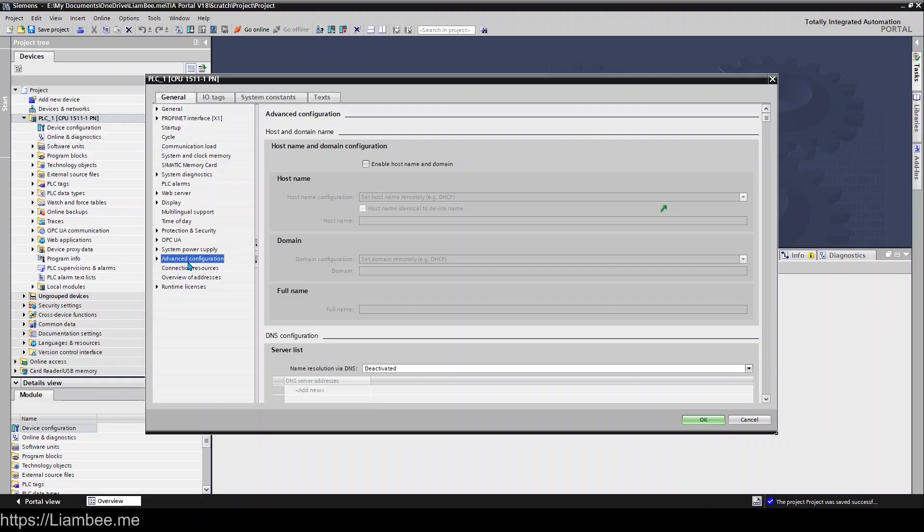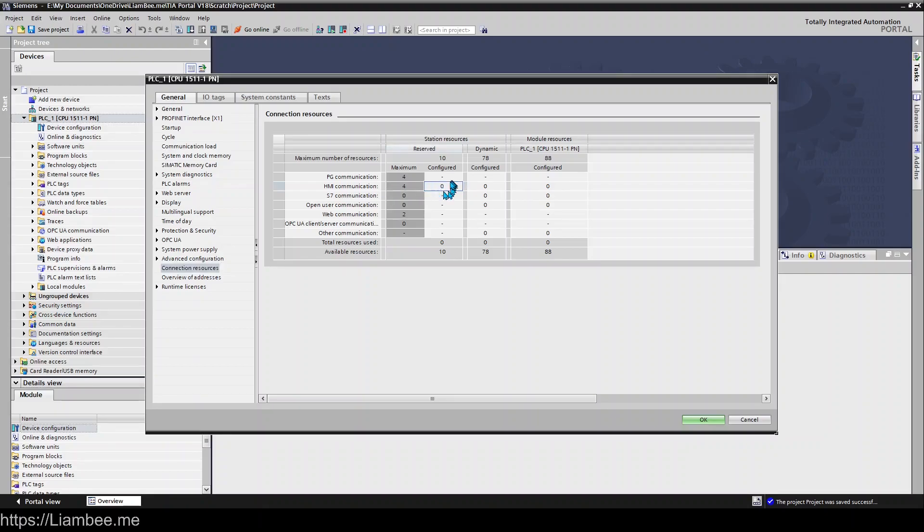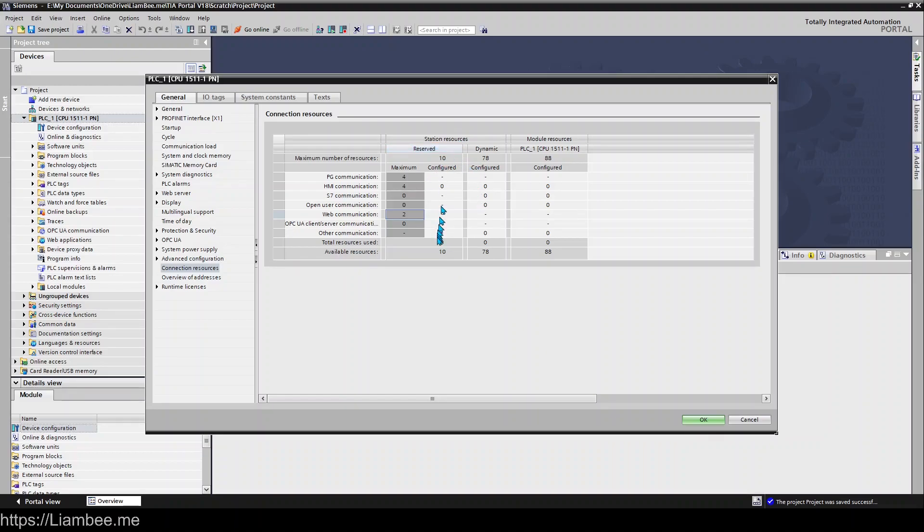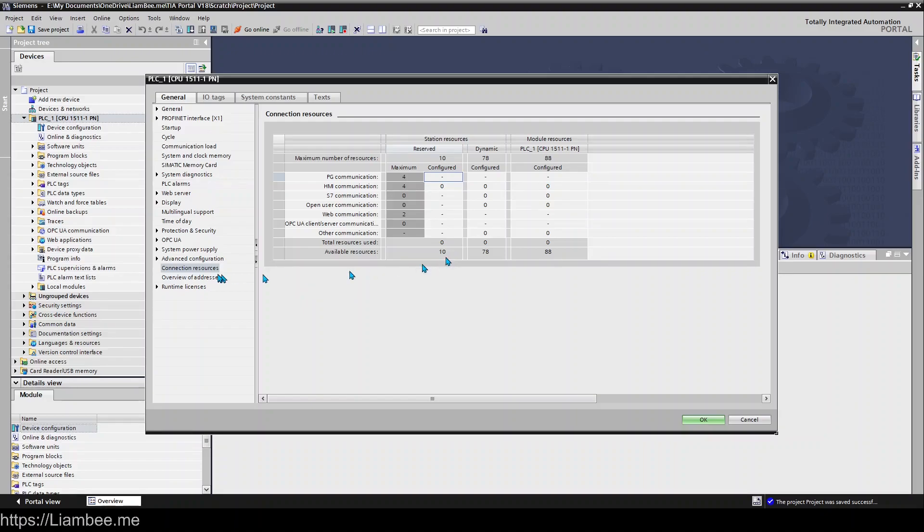So connection resources tell you how many PG connections you've had HMI communication connections you've used so we can see here that this PLC is capable of using up to four HMI communications. It can use two web communications and overall it has 10 station resources. I'm not quite sure how they get to these numbers because looking at this you can't configure these anyway. So PG communications and stuff you can't configure them they're used when something is connected but you'll find that if too many people or too many connections are being made you run out of resources basically and this is just where you can come in and have a look at what you've got available to you that you can't actually change anything in here.